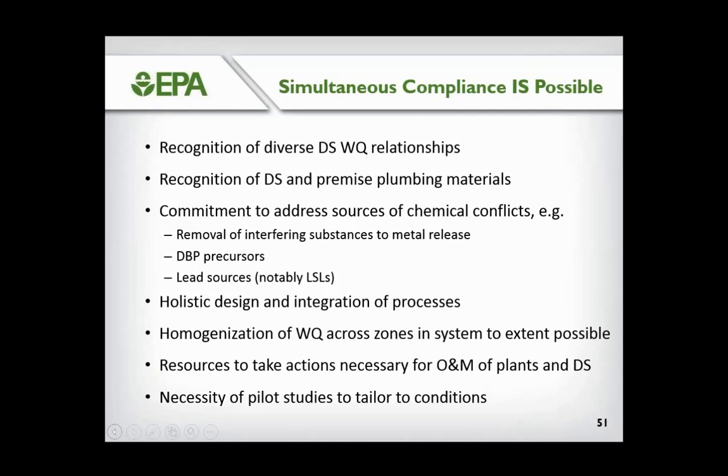Okay, so simultaneous compliance is possible if you recognize the diverse relationships, recognize what distribution and premise plumbing materials you have, because certainly if you've got lead pipes in place, you've got a lot more complications than you do if you have a system that only has lead in brass devices or in lead solder joints.